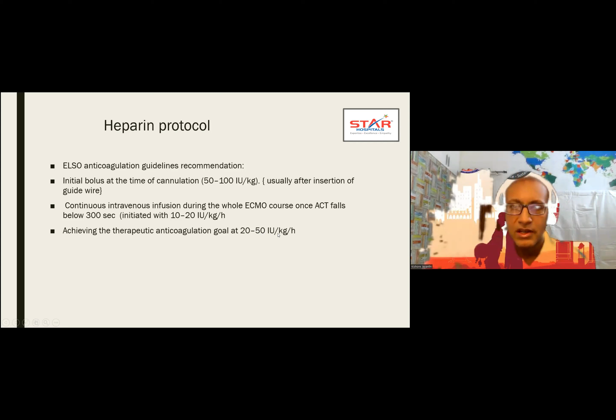The target dose for therapeutic anticoagulation is basically measured by activated clotting time, which is called ACT in short form. Usually we maintain it around 180 to 220 seconds, but we can also maintain it a little lower in case of minor oozing or bleeding in some patients. You can see the ACT machine on the right and the container for the blood. Here we take the blood sample in this and immediately put it into the ACT machine after calibration to the normal ambient temperature. Once this sample goes in, it reads the time duration for the clotting. So usually we keep it around 180 to 220 seconds.